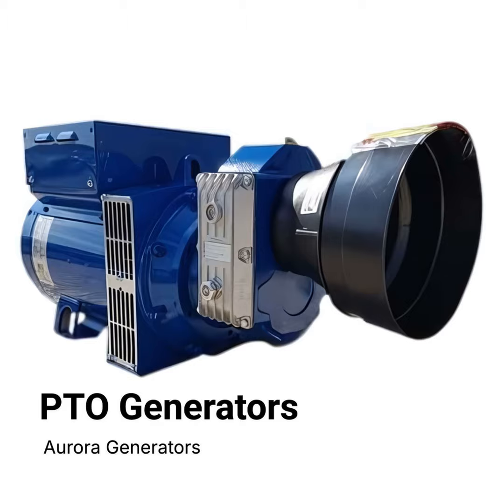So if an alternator could run hotter, because it has Class H insulation, but it's designed to run cooler in normal operation, does that help it last longer? Absolutely. That's a key point. If you operate an alternator well below the maximum temperature limit of its insulation class, you're putting much less thermal stress on it. Less stress equals longer life. Significantly longer, potentially. It slows down the natural degradation process of the insulation. Conversely, if you consistently run it hotter than its design temperature limit, even if it's within the insulation class capability, you will shorten its lifespan.